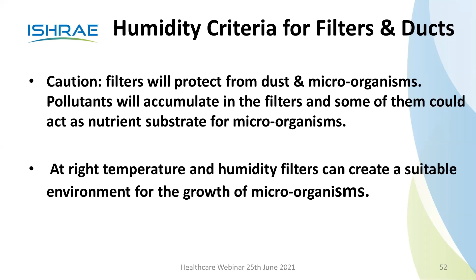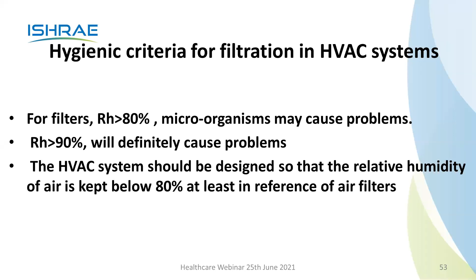At right temperature and humidity, filters can create a suitable environment for growth of microorganisms. For filters, RH more than 80%, microorganisms may cause problems. More than 90% will definitely cause problems in terms of mold growth. The HVAC system should be designed so that relative humidity of air is below 80% with respect to air filters. What does that mean?